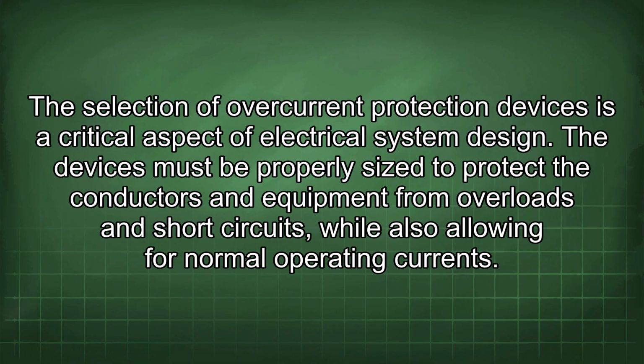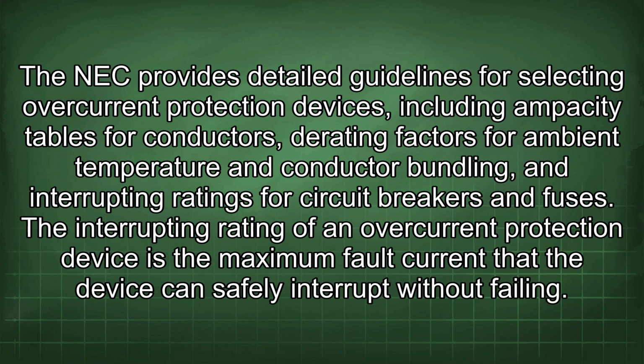The selection of overcurrent protection devices is a critical aspect of electrical system design. The devices must be properly sized to protect the conductors and equipment from overloads and short circuits, while also allowing for normal operating currents. The NEC provides detailed guidelines for selecting overcurrent protection devices, including ampacity tables for conductors, derating factors for ambient temperature and conductor bundling, and interrupting ratings for circuit breakers and fuses.